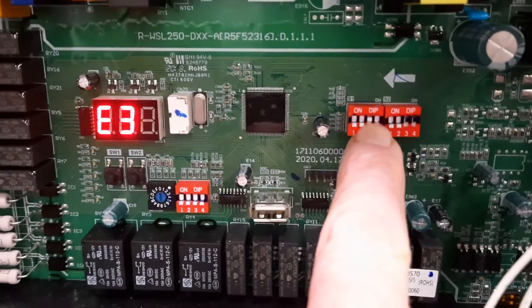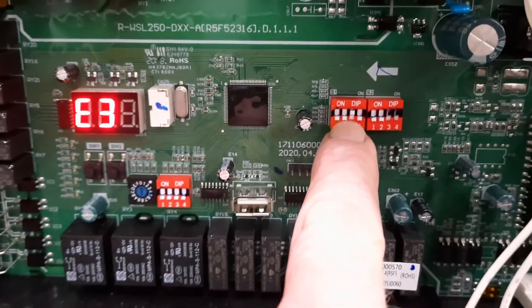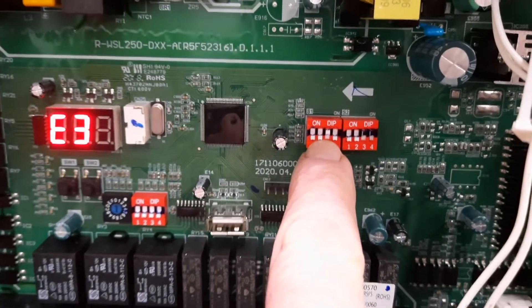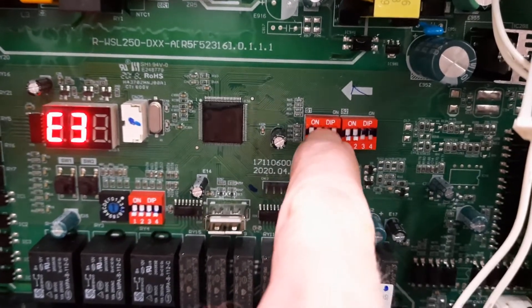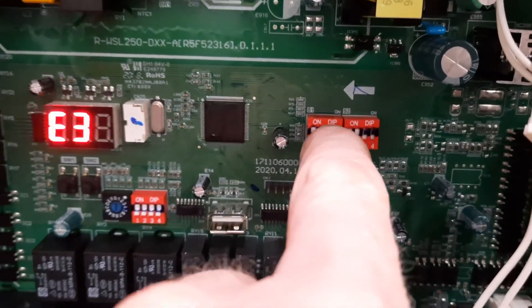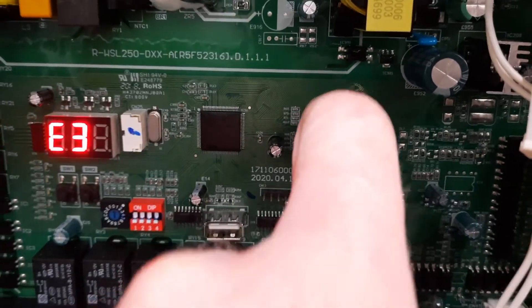you can see they should normally all four be down but somebody has flicked one of them up, this one here.